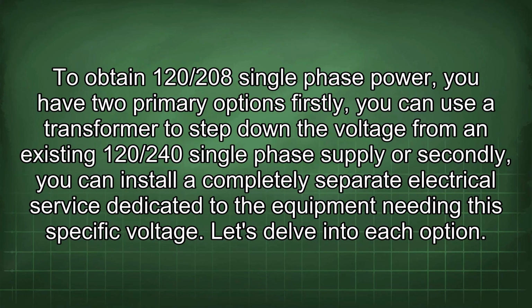To obtain 120/208 single-phase power, you have two primary options. Firstly, you can use a transformer to step down the voltage from an existing 120/240 single-phase supply, or secondly, you can install a completely separate electrical service dedicated to the equipment needing this specific voltage. Let's delve into each option.